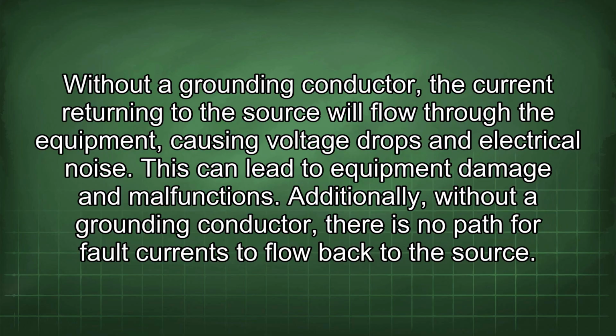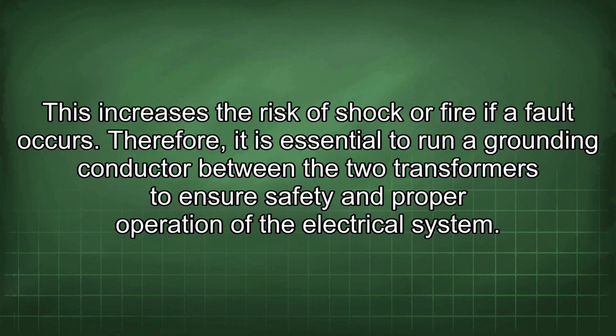Without a grounding conductor, the current returning to the source will flow through the equipment, causing voltage drops and electrical noise. This can lead to equipment damage and malfunctions. Additionally, without a grounding conductor, there is no path for fault currents to flow back to the source. This increases the risk of shock or fire if a fault occurs. Therefore, it is essential to run a grounding conductor between the two transformers to ensure safety and proper operation of the electrical system.